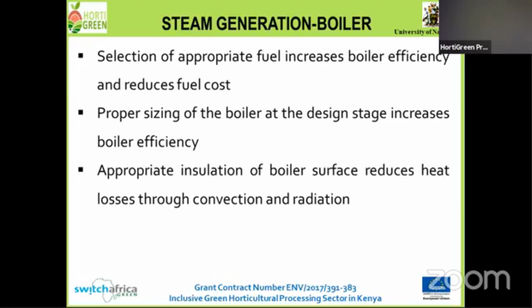And there is need for insulation. Heat is lost from boilers, from the boiler surfaces, through what is referred to as convection and radiation. And insulation is recommended, proper insulation. Now, steam pressure needs to be controlled, because the higher the pressure, the higher the energy consumption. And therefore, you generate at the minimum pressure that is needed for your operations.